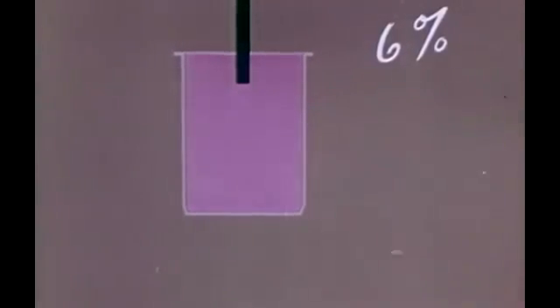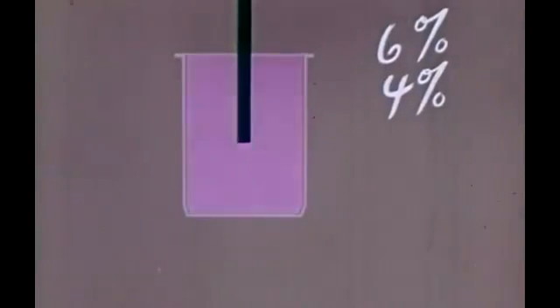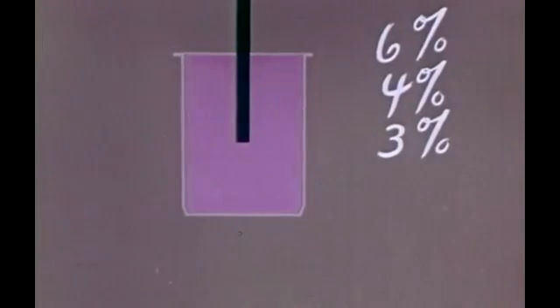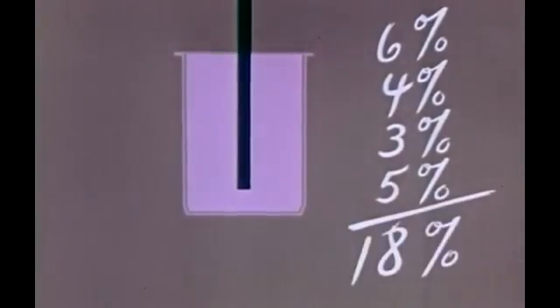Initially, there must be sufficient reactivity to sustain criticality, or a neutron multiplication constant of 1, or unity. The excess reactivity was designed to include 6% for fuel depletion, 4% for fission product poisons, 3% for temperature changes, and 5% for design margin to allow for the uncertainties in the design of this unprecedented type of core. The total of 18% excess reactivity was selected as the optimum. More might cause difficulties with operation and shutdown; less, either no criticality or shortened life of the core.